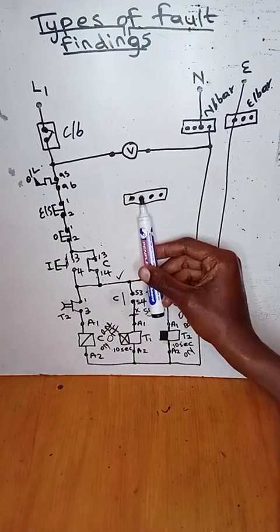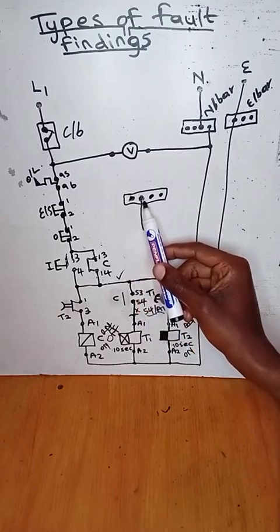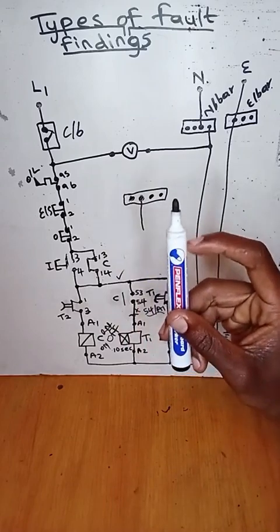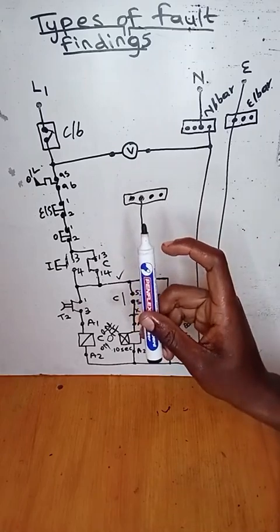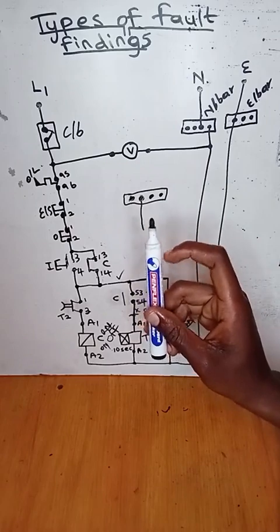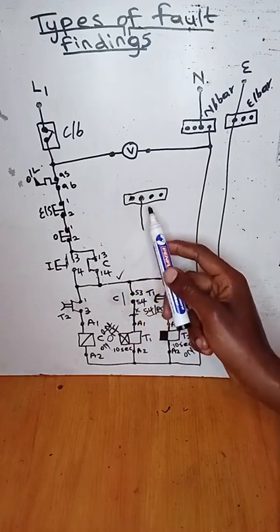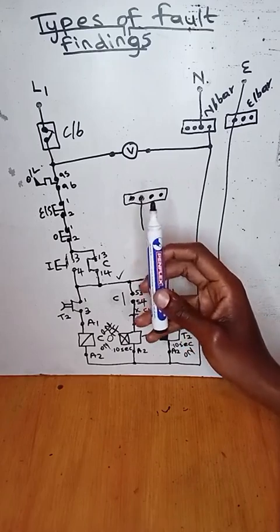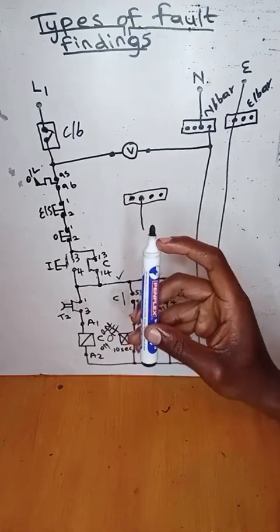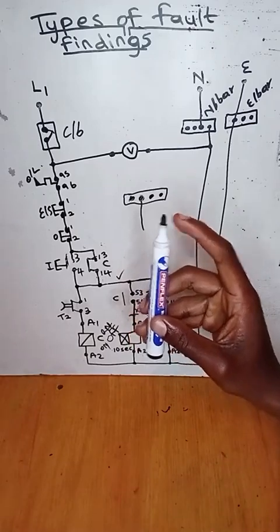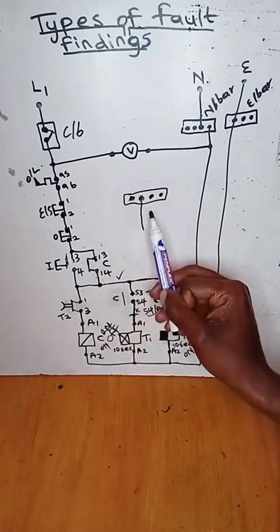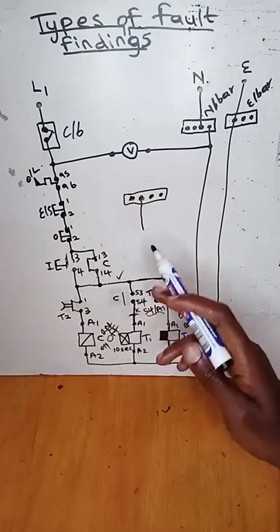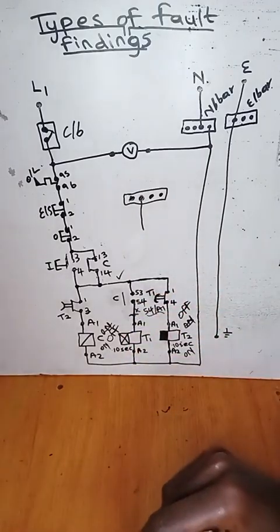You must connect it to the copper so that it can be present, because if you connect it to the insulation and test continuity, it will tell you that the wire is absent, and that will be tricky for you, because you'll see that the wire is connected, but you won't know that the wire didn't touch the copper. So you must be very careful about that one, right? Make sure you do your connections right. So that's another fault that you can find.